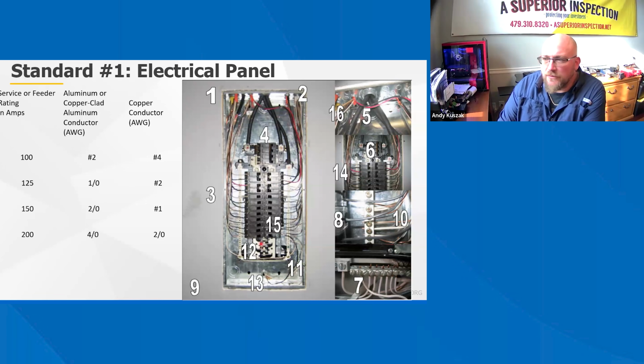Number 12, down over here. The main bonding jumper must be installed to connect the ground and neutral bars and make connections to the enclosure. Number 13, all unused holes in the panels should be closed. Number 14, right over here, white insulation conductors that are used as ungrounded conductors or hots should be identified at all termination points, meaning a lot of times you'll see black tape wrapped around a white conductor.